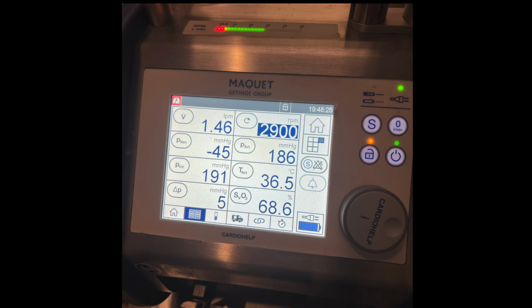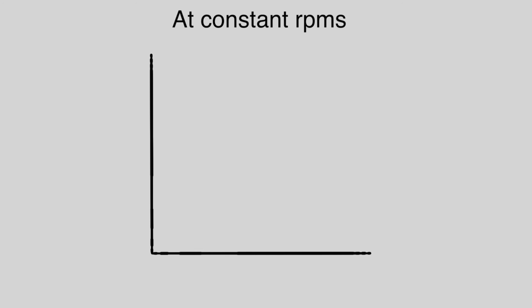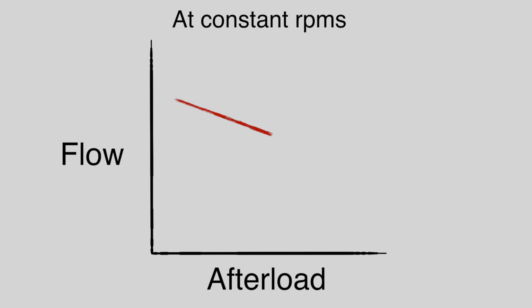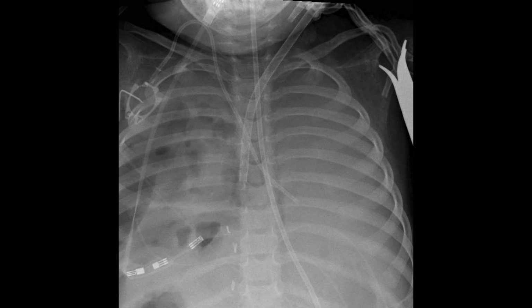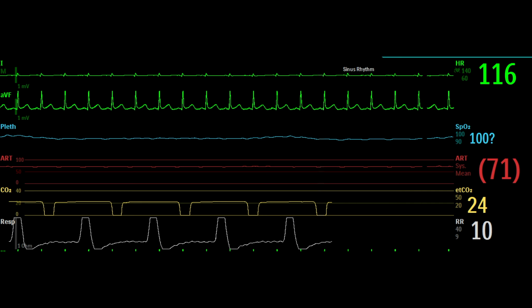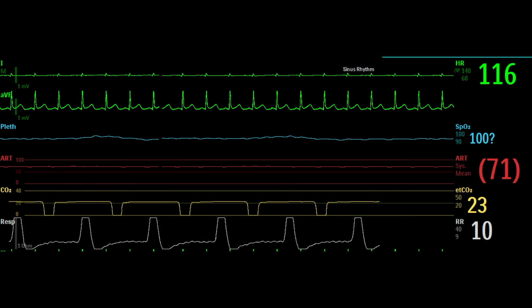The pump is also sensitive to afterload, which is how much pressure it's having to generate to pump blood out of the circuit into the body. The higher the afterload to the pump, the less flow there will be for a set amount of RPMs. High afterload can be the result of a couple of things. It may be a mechanical issue, with cannulas that are too small for the flow you want, or not well positioned. Or it can be a patient issue, with high systemic vascular resistance and hypertension.